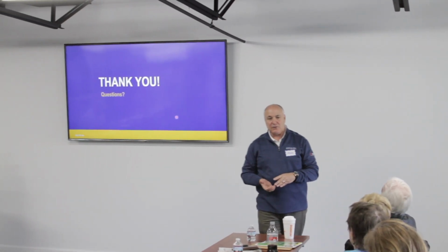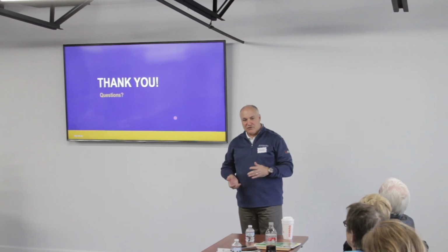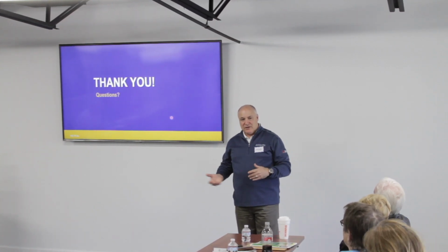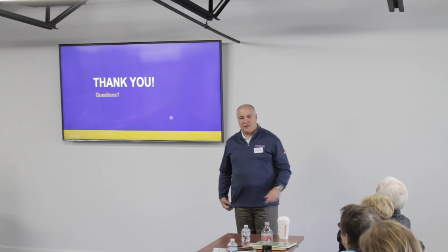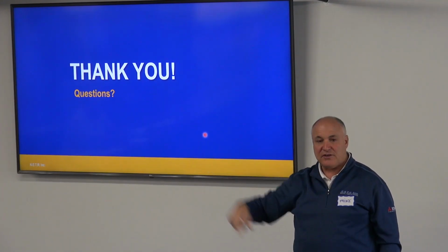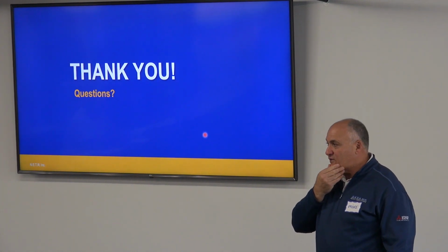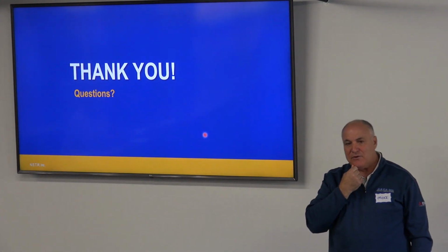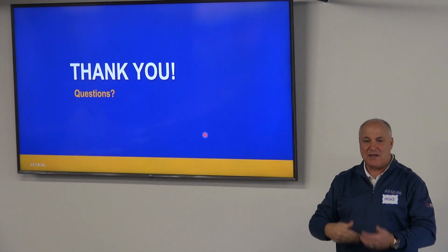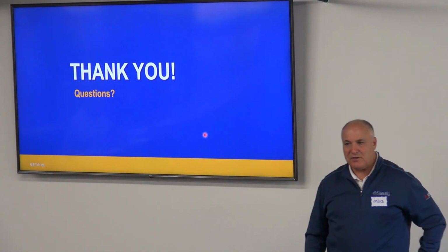What kind of square footage with 18,000? As a good rule of thumb, for every 400 square feet of space you have, it's roughly about 12,000 BTUs. So a 200 square foot bedroom is like a 6,000 BTU unit. When we get into the bigger homes, the units get bigger. We go anywhere from 6,000 up to 60,000 on the residential series. That unit can go up to 60,000 BTUs, and you can run 8 units off of that into the 5-ton range. When we say 5 tons, it's 12,000 times 5 is 60,000, so that's a 60,000 BTU system.